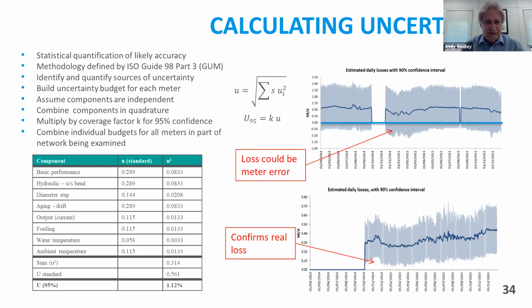And we use statistical techniques around combining those components in quadrature, so root mean square sum, to work out what that overall uncertainty is. And then we can look at that at different confidence levels. So one would normally do it at a standard confidence level, 68% confidence level. But then if you want to look at a 95% confidence level, you effectively double that by multiplying by the coverage factor, which is around 2 for 95% confidence. So we can build up uncertainty budgets for all our meters that take into account all these unknowns, all these sources of potential error. As I say, we don't know whether they're happening. We're in the world of probability here rather than absolutes. And we can find out what our expected uncertainty is for each of the meters in our system.